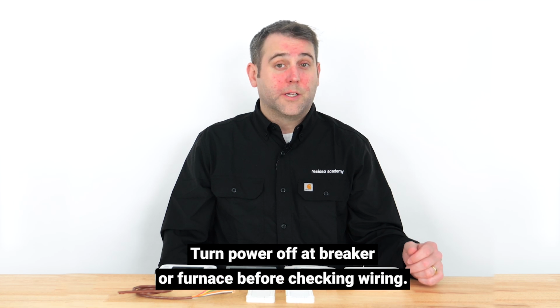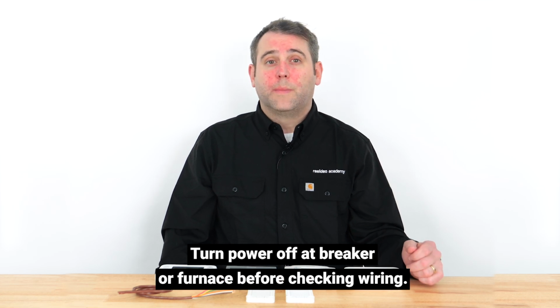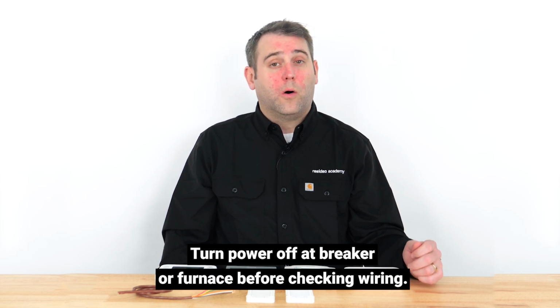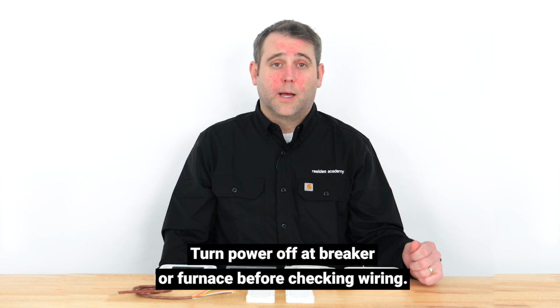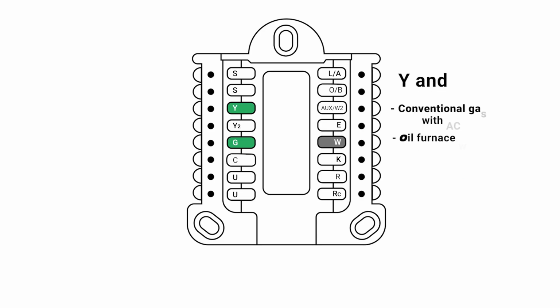If compressor protection isn't the issue, check the wiring based on your system type. Confirm all the wires are in the correct terminals with good contact. The Y and G terminals control cooling for most conventional gas or oil furnaces with an air conditioner installed. The Y, G, and sometimes O/B terminals control cooling for a heat pump system. The Y2 terminal controls additional cooling stages.